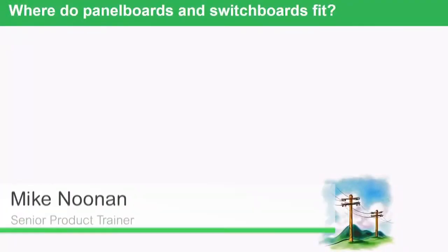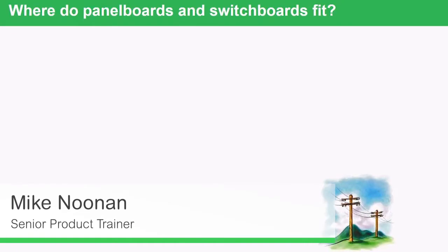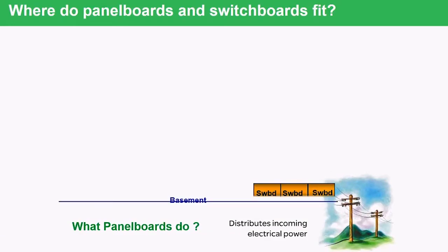To look at where a switchboard fits compared to other products in the distribution world, we'll take a look at a building. The switchboard is usually the terminating point of the utility conductors. The larger the facility, the larger the switchboard, and it is more likely that a large facility would have a switchboard as the main point of entry for the service entrance.